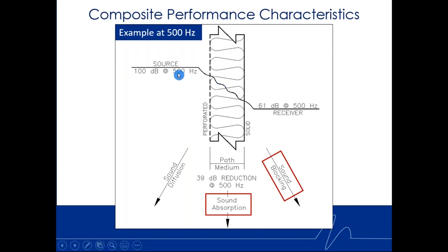So when you actually exit and break through that outer solid shell, you might, for this example, at 500 hertz, go from 100 dB sound power level to 61 dB. A huge reduction, and that's due to sound blocking and a function of the mass and the thickness of the panel and the insulation. On the inside, you get a little diffusion of the noise. Then after it hits this solid surface, some sound energy is going to bounce back, go through the absorptive material again, and then some of that sound energy is going to come back into the open space. So on the side of the noise source, it is actually going to be reduced a little bit as well, because it gives you absorption. Once again, you get sound blocking and you get sound absorption. Moving from 100 dB to 61 dB, you take the straight difference and come up with a 39 dB reduction, and that's considerable.